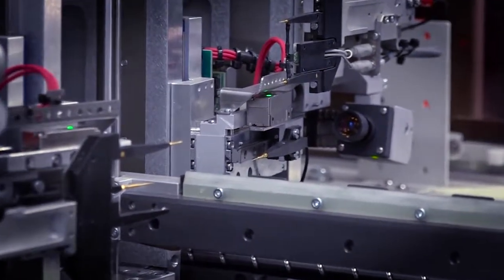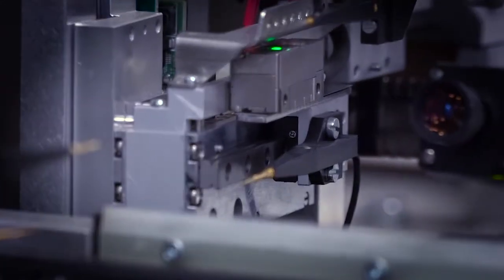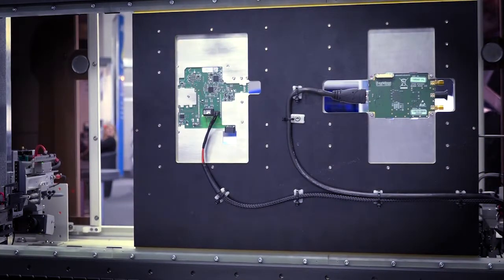The secret is to compensate for the fact we have long cables, so we can do high frequency measurement even if we have meters of cables in the machine. So these are specially shielded cables that you're using. Correct. And when you're grounding it against the carrier plate here on the device. Yes, the unit under test is mounted on a carrier, and the carrier is part of the measurement because it grounds the machine. The unit under test, and it gives a shield for the RF measurement to the DUT.